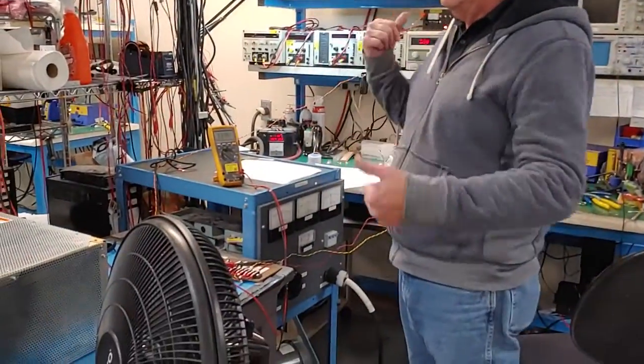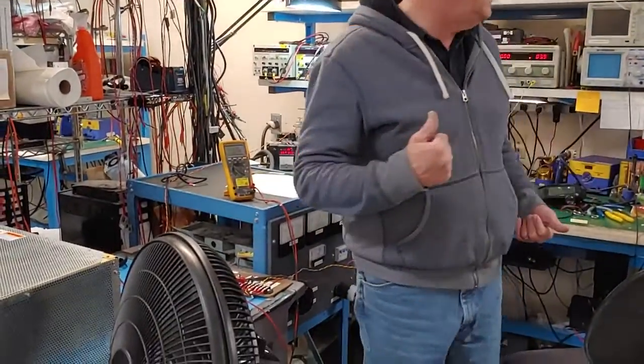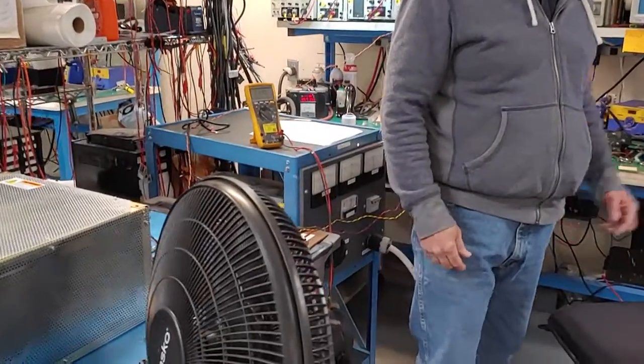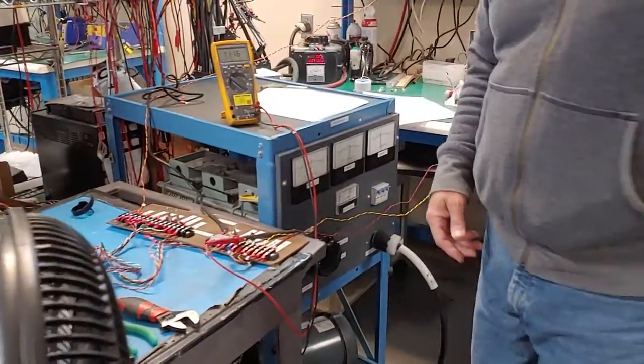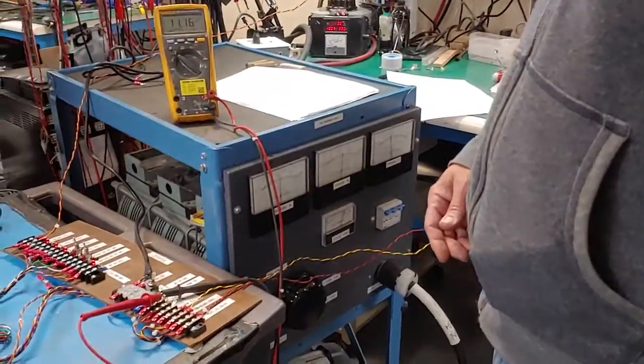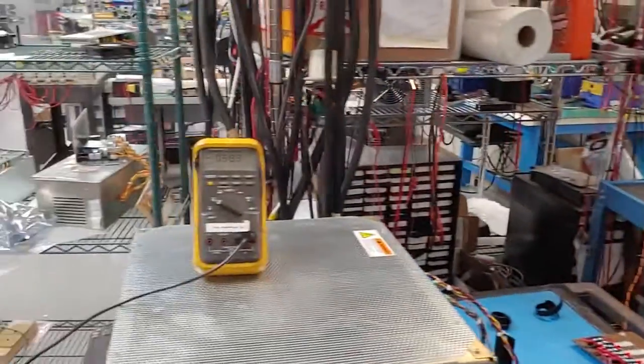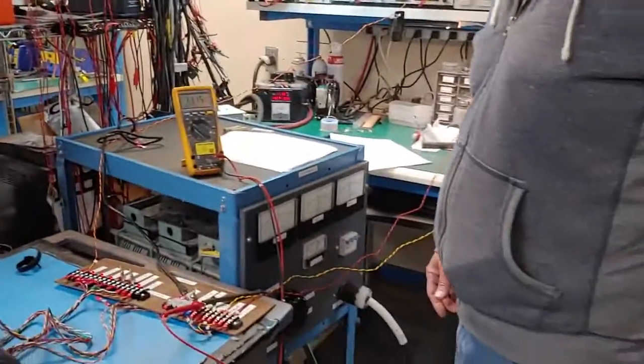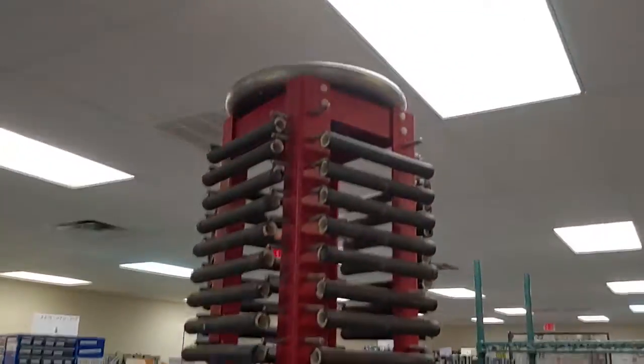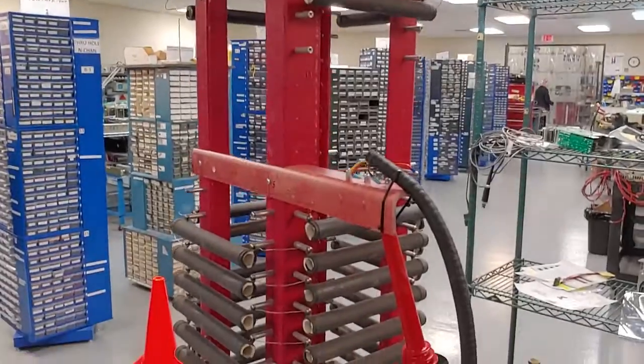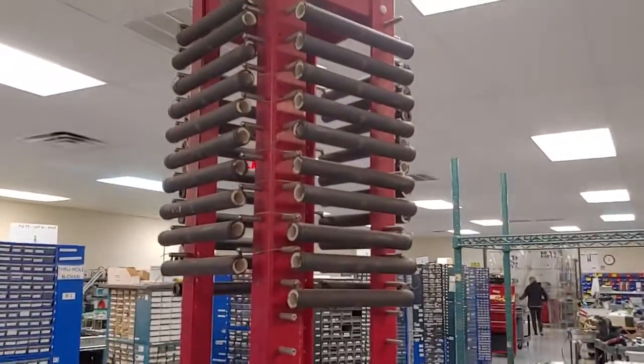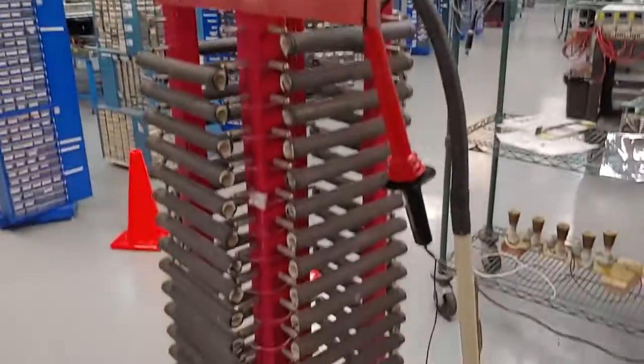Okay, this was started up at about 10 o'clock this morning. It's currently 12:27. She's been fully running. All right, what we're going to do is take it down and bring it back up and demonstrate the process of how we're clearing this. That's the load over there at 60,000 volts at 40 mils, and the small top resistor is our filament. It's loading to about 60 watts for the filament.